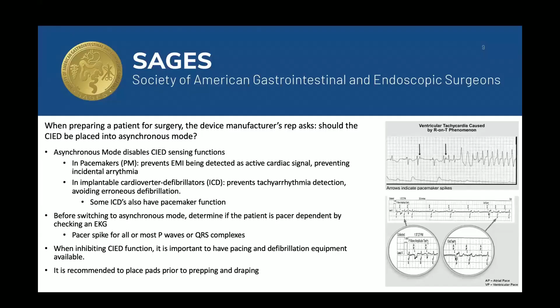Going back to the text, there's another kind of device, the defibrillators, and what you do when you put them in the asynchronous mode is you prevent the tachyarrhythmia detection. So if the patient is prone to arrhythmias and needs or is at risk of essentially a ventricular tachycardia requiring defibrillation, you're turning that device off. And so that is helpful if you don't want that to happen. But when you do that, you should really think about what your anesthesiologist needs to have prepared just in case that happens to the patient while their implanted device is not available. And so that usually means if a patient is prone to this problem, you should put pads on them before you prep and drape. So that way the anesthesiologist has the option to defibrillate them, God forbid something were to happen, even though it's probably not that likely. The time to do it is before you get into the surgery.